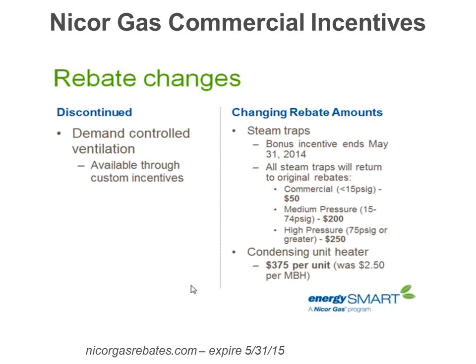So you could still do DCV rebates with CO2 sensors. You just have to do it as a custom application because they got to be able to decipher how you're using it in your building. Because some buildings, like a VAV system, it doesn't make sense on the heating side. It still makes sense on the cooling side, with electric, but not on the heating side. So that's why that's changed.